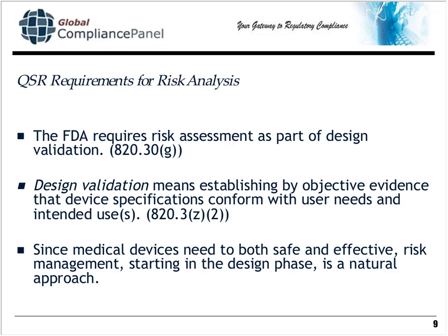So what this means is you want to make sure that as part of your validation that you understand your user needs, the intended use of your device, and that you demonstrate that you meet the user needs and intended use. And the user needs are medical devices that are safe and effective. And so this is why risk management is in design validation in the FDA regulations, because it is part of the work that you do to demonstrate that your device is safe and effective. And it tends to focus more on the safe side than on the effectiveness side, but that's why it's in design validation in FDA QSR.